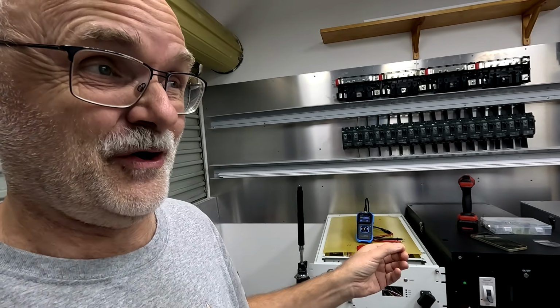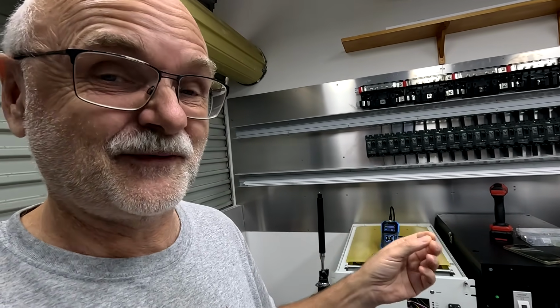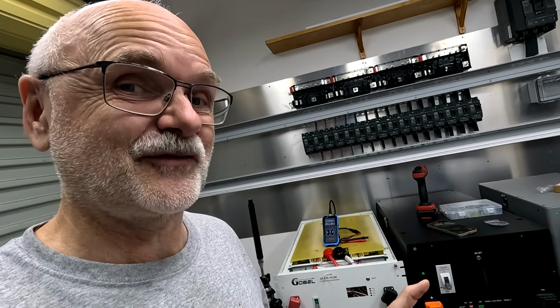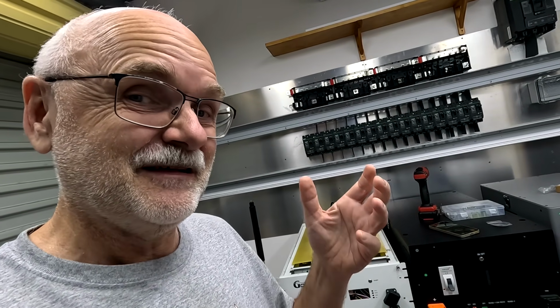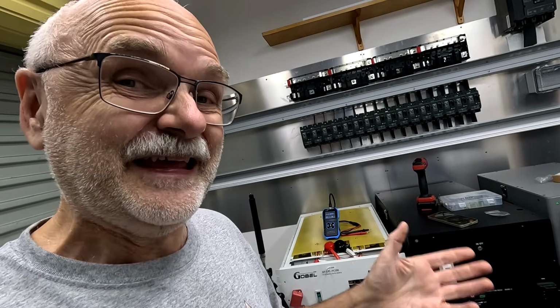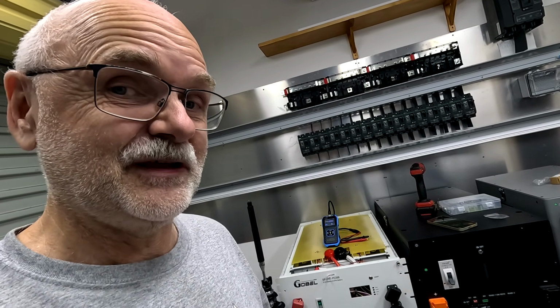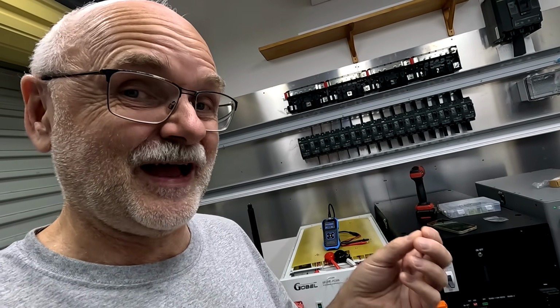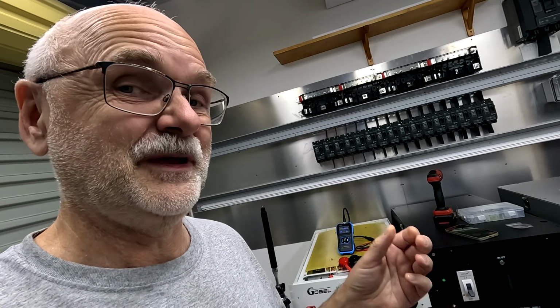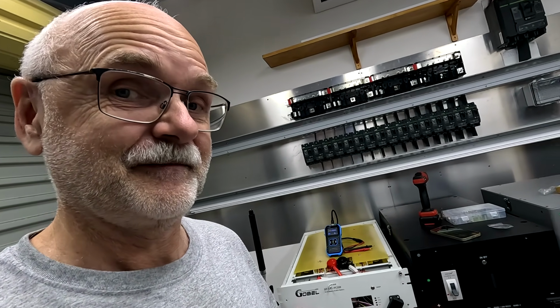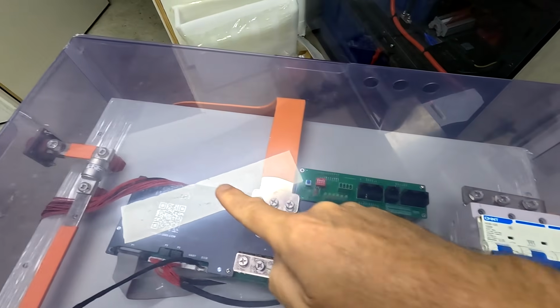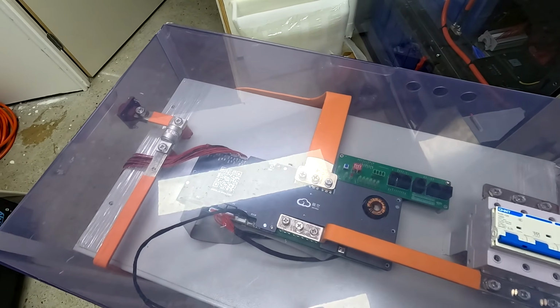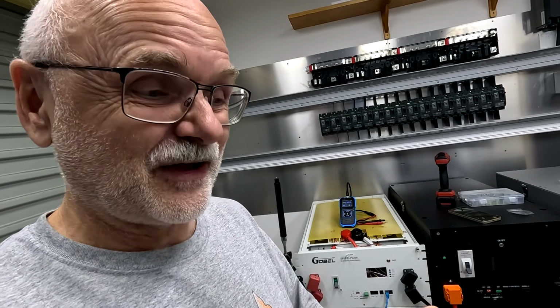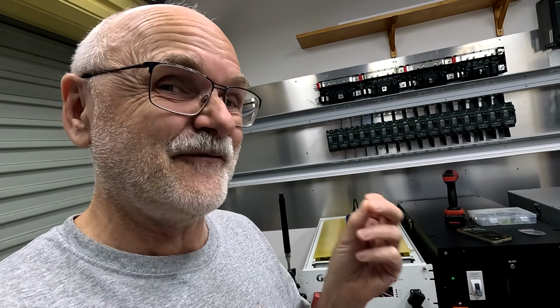Once this occurs and there are 20,000 amps flowing in this battery, obviously the chemistry inside such a battery is changing. Chemicals are decomposing. A lot of heat is generated, of course. So we can safely assume the overall internal resistance goes up and therefore the short current will go down. But the first initial short current will be over 23,000 amps. And neither the breaker nor the fuse can safely disconnect this amount of current.